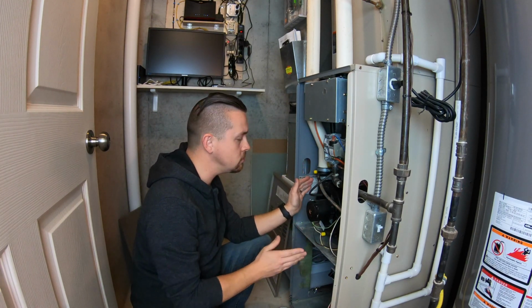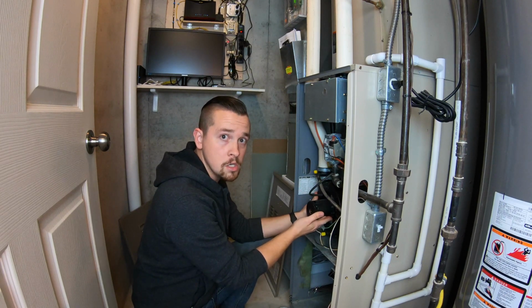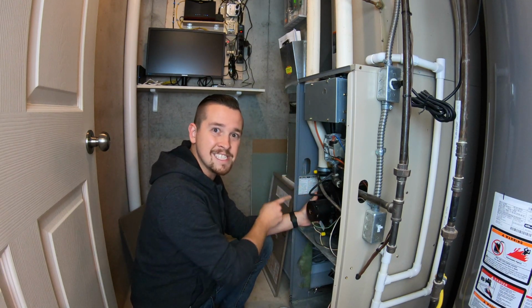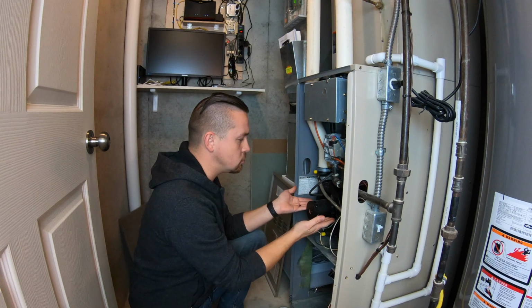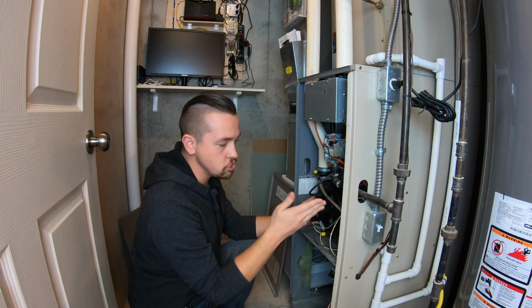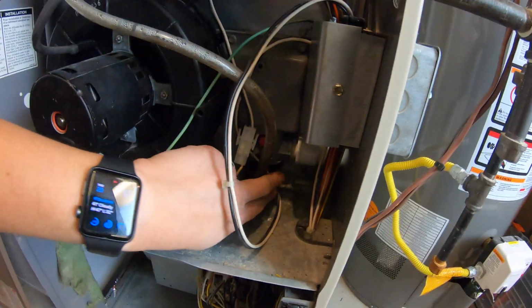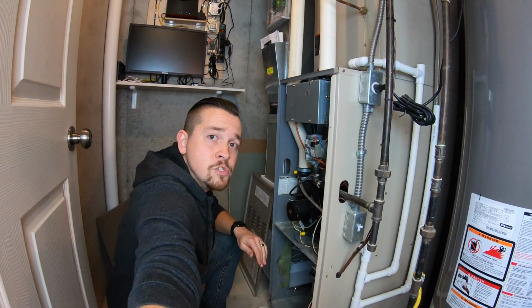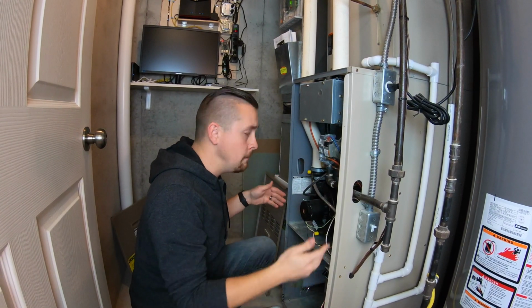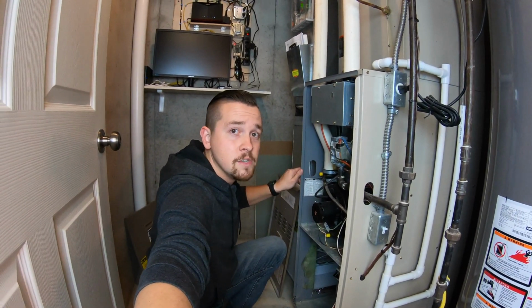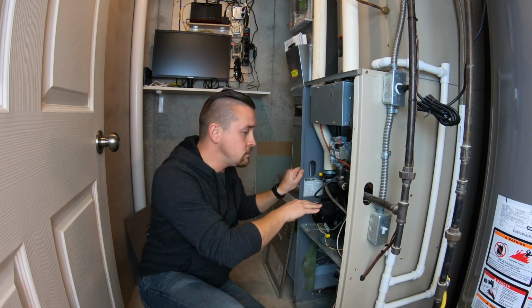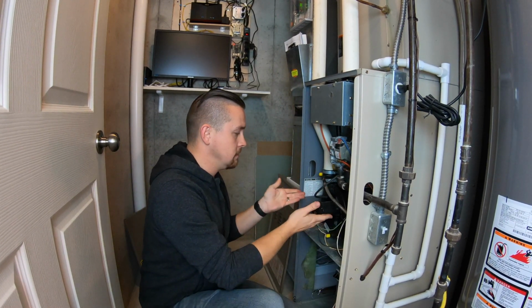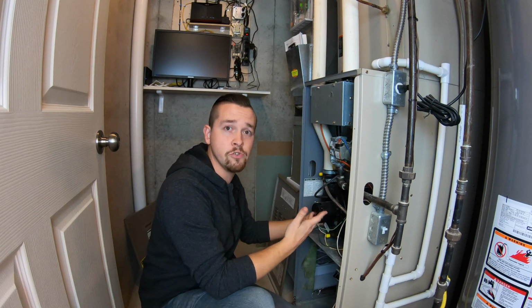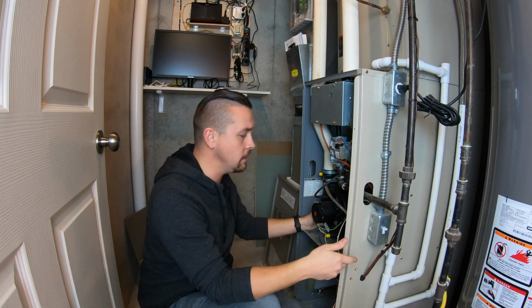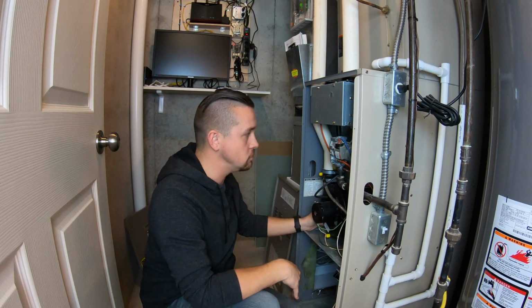Another thing that can happen too is this can actually get full of water, and then that motor can't spin the wheel anymore because there's water inside of this inducer because your drain is plugged. I showed you this drain trap here. That guy can get plugged up, and if water can't drain out of the system, it has nowhere else to go but down into that inducer assembly. And it's actually fairly common as well that that inducer can't spin because there's water inside of there. So make sure that you clean your drain trap occasionally or have a technician do it for you. Clean the drain system out to make sure everything drains properly.